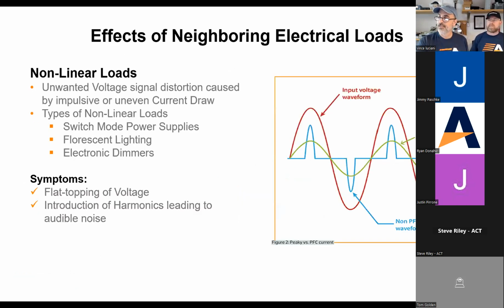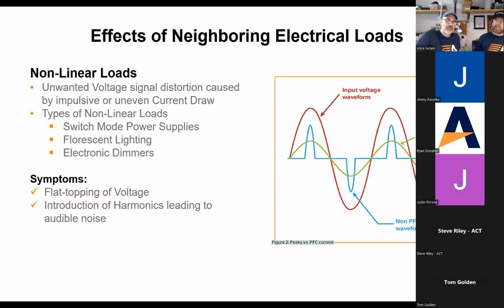So noise and power disturbances are not the only thing that is screwing up our power. We just got off a call with another manufacturer. That manufacturer was saying, good Lord, the number of switch mode power supplies that we have in our systems, they're backfeeding noise back onto our line. Because remember, even if we're using dedicated lines, I've got a dedicated 20 amp circuit for rack 1 and another dedicated one for rack 2. Well, everything in rack 1 is on the same power bus, and it's all going back to possibly the same panel, same sub panel, and could be disturbing other equipment. Yeah, absolutely correct.